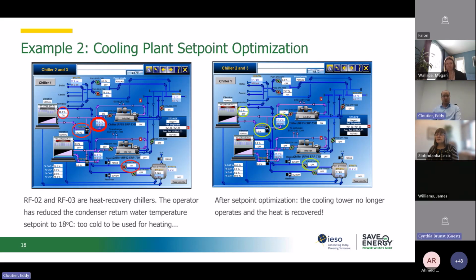Unfortunately, during recommissioning, we discovered that the operator had not been adequately trained or had not understood that to operate, the chiller discharge temperature adjustment must absolutely be above 30 degrees Celsius. And that's what we see in the picture on the left. He had adjusted the rejection temperature to 18 degrees Celsius, which caused all the heat to be rejected to the cooling tower that we see on the left. And it also caused a freezing problem at the cooling tower during really low outside temperatures.